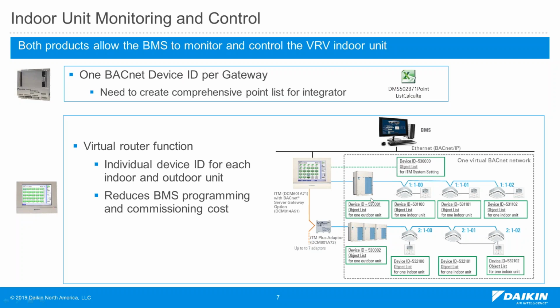So with this function, each indoor unit has an individual device ID, and they share the same exact object list. Each outdoor unit also has an individual device ID, and the object list for the outdoor units is the same. The ITM itself also has a device ID, and it has its own object list for just the ITM system setting. So the user can easily assign these IDs and choose the objects they want to control.